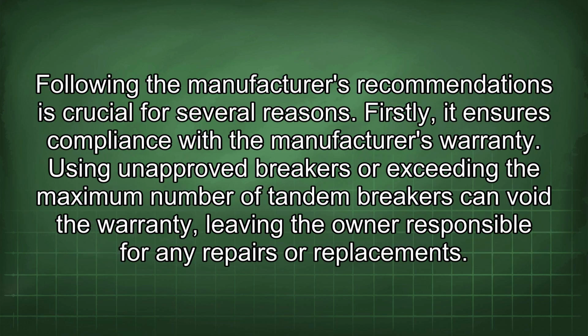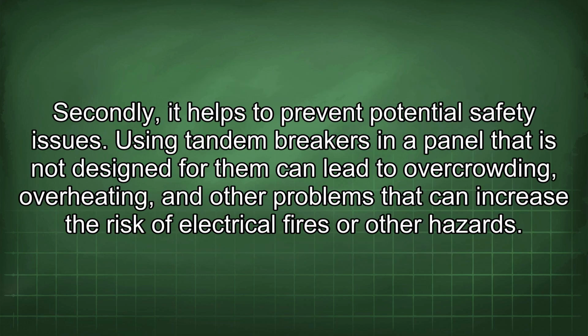Following the manufacturer's recommendations is crucial for several reasons. Firstly, it ensures compliance with the manufacturer's warranty. Using unapproved breakers or exceeding the maximum number of tandem breakers can void the warranty, leaving the owner responsible for any repairs or replacements. Secondly, it helps to prevent potential safety issues. Using tandem breakers in a panel that is not designed for them can lead to overcrowding, overheating, and other problems that can increase the risk of electrical fires or other hazards.